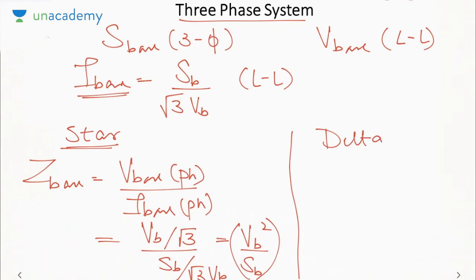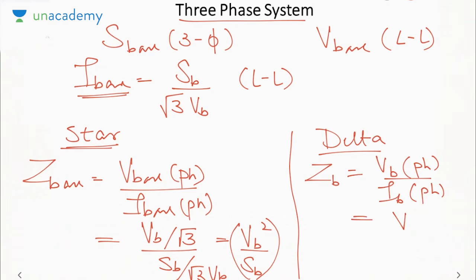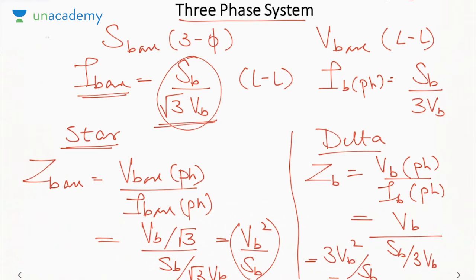What about a delta connection? Z B will be equal to V B phase over I B phase. Now V B phase will be the same as the line voltage, that is V B, but I B phase will be equal to the line current divided by root 3, since in delta connection phase current is equal to line current by root 3. So I B phase for a delta will be S B by 3 V B. So this will come out to be 3 V B square by S B, that is 3 times the star. That is understandable, because when we convert an impedance from star to delta, we get a factor of 3. The same factor comes in the case of base impedances. So remember, the base impedance for a star and a delta connection will be different.